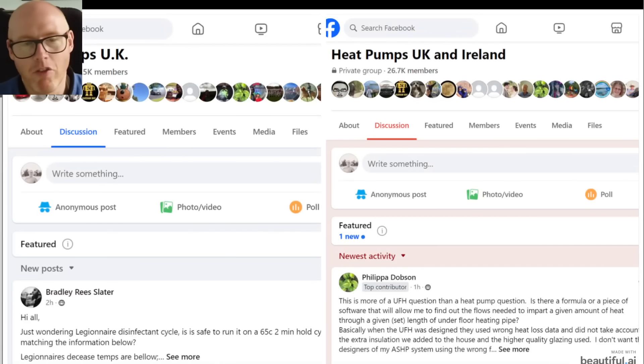Once you've got that information, go into one of these groups and lay that data out as clearly and concisely as you can, and you will get some sensible, reasonable responses. The responses may just be: yes, that's correct, that's how much your heat pump should be costing you. Or it may be: your flow temperature is too high — maybe you need to lower your weather compensation curve. What we see a lot in these heat pump Facebook groups is that installers don't want to leave people cold, rightly so — they don't want people to experience discomfort. So the default weather compensation curve is always multiple steps higher than it should be. Only you as a homeowner living there can dial it in over time; you can just adjust that weather compensation curve down and really reduce your costs.